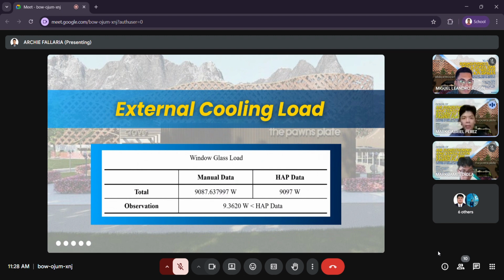Moving on to the glass load under the external load, another important factor is the total heat load from the windows. This is much higher than that from the walls and roof because of the restaurant's large glass areas. Manual calculations show the windows contribute around 9,087.64 watts of cooling load based on both solar heat gain and thermal transfer through the glass. This closely matches the HAP software results.